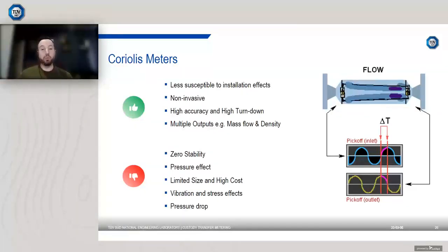Now, obviously, they've got a number of advantages. What are the disadvantages? Well, zero stability can have an impact. So when there's no flow going through a Coriolis meter, the meter should indicate zero under ideal conditions, but in reality, small changes in temperature, pressure, vibration, ambient effects will result in the meter indicating a flow when there is no flow. So obviously, to account for that, you need to zero the device. But over time, the zero can drift, and depending on the flow rate you're trying to measure, it can have quite a big impact.